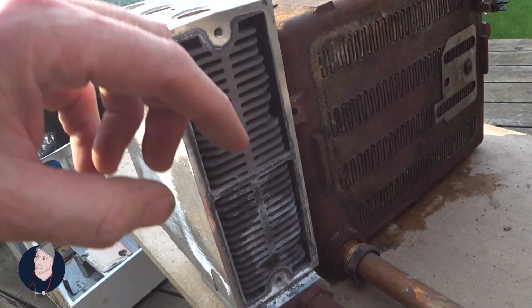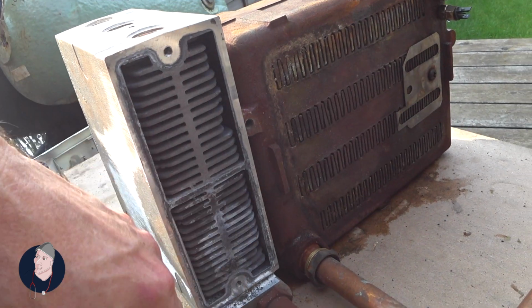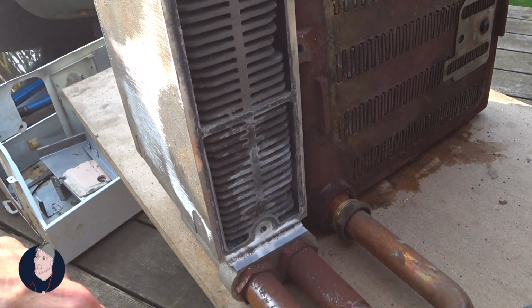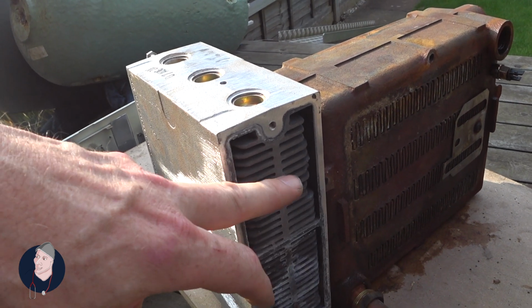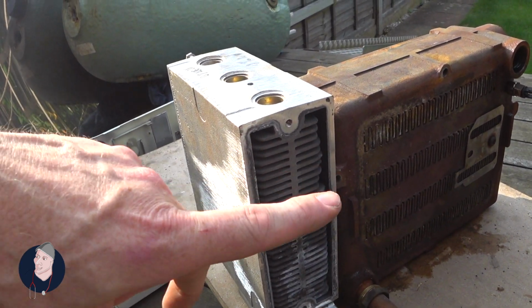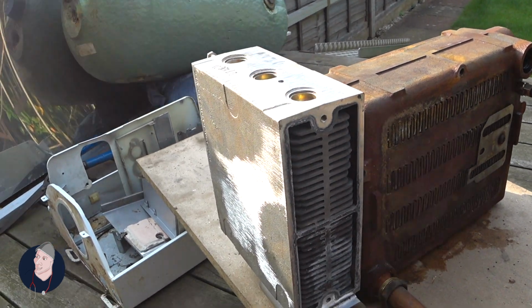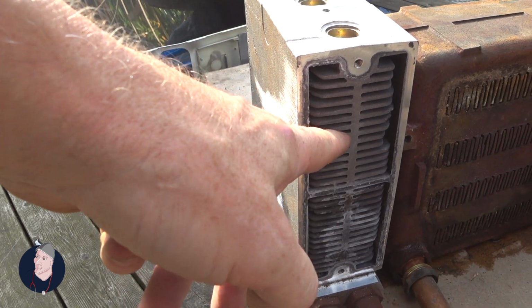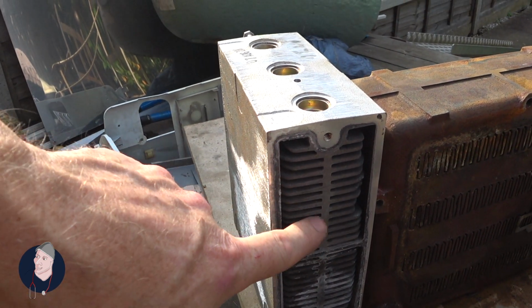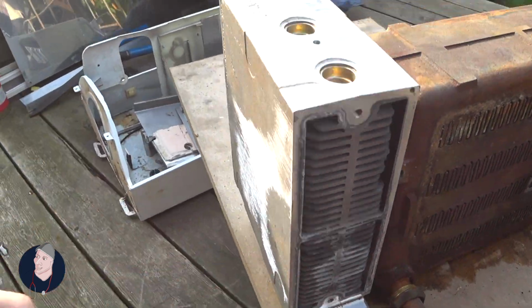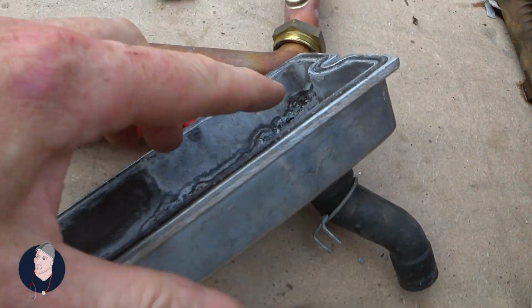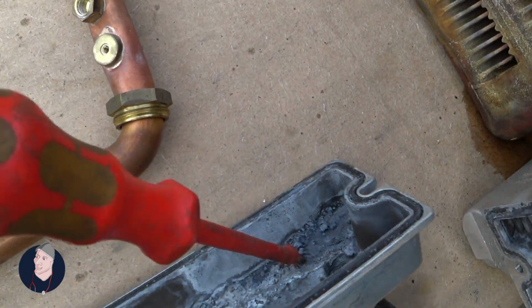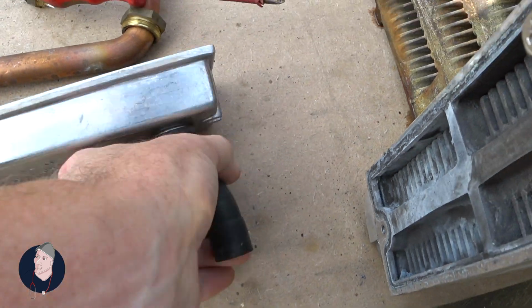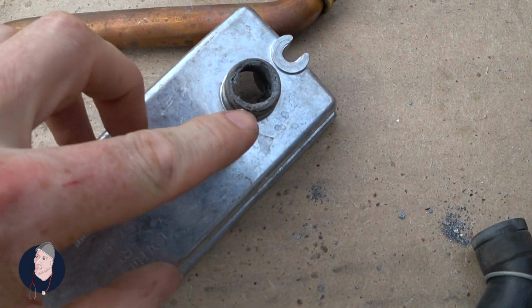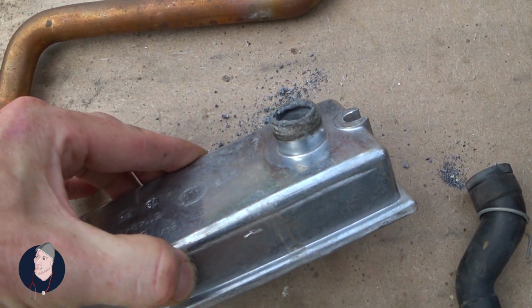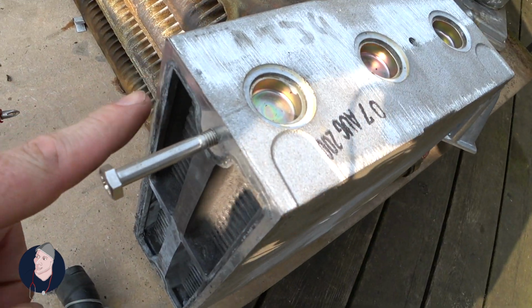Meanwhile, inside of here, it can create blockages and this aluminium oxide. The aluminium oxide is because the condensate water is acidic and the aluminium is reactive against acids. So what it does is it degrades, hence you get this grey material. And if you look on here, you will see the pitting and the way it deforms and degrades, so you can get corrosion on the seals.